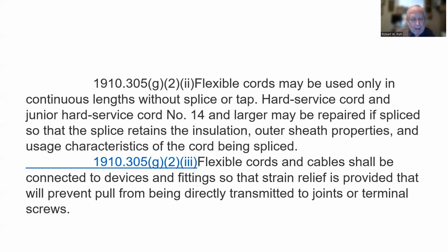Flexible cords and cables shall be connected to devices and fittings so that strain relief is provided that will prevent pull from being directly transmitted to joints or terminal screws. If you have drops coming down from the ceiling, you look up there and you'll see that the cord comes down, and then there's a hanger coming down, and the cord goes through it before it drops down, and that's your strain relief. So there's strain on that cord, including just the weight of the cord, and that's usually a little bit flexible. It won't be pulling the cord where it goes in the junction box.